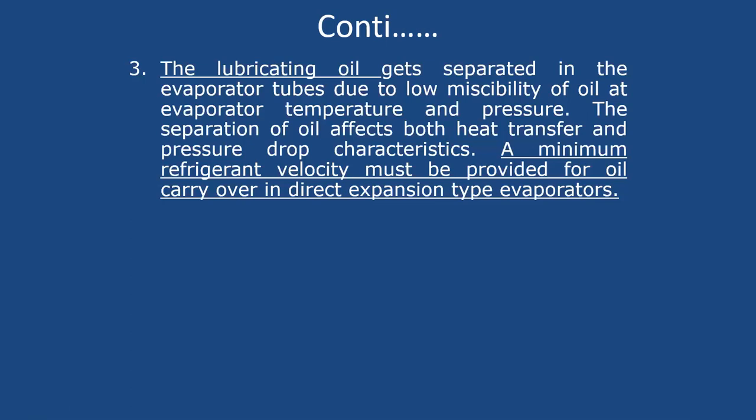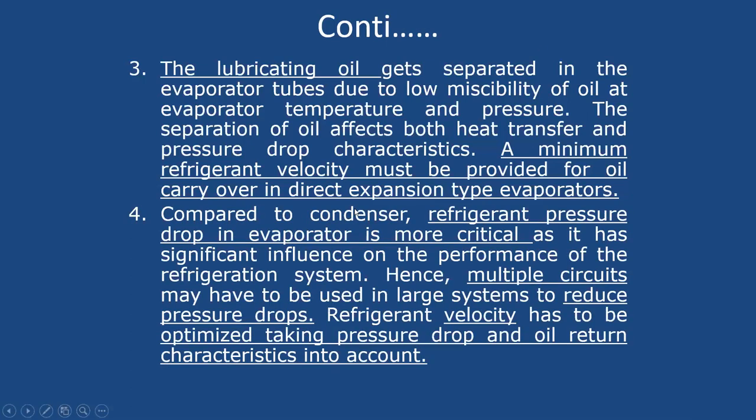So the adequate velocity has to be maintained. A lot of simulation work is required while deciding the refrigerant velocity. Compared to the condenser, refrigerant pressure drop in the evaporator is more critical, obviously, because it is more sensitive to the cooling capacity as far as reciprocating compressors are concerned, as it has a significant influence on the performance of the refrigeration system.